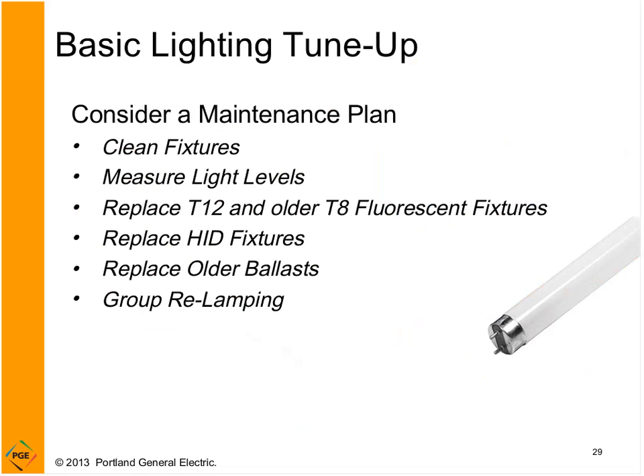Moving on to maintenance of lighting systems. You want to make sure you clean the fixtures. You can measure light levels to make sure that lighting is adequate. Many times, especially if you've got an older facility, maybe the lighting has been retrofitted, but maybe they did a one-for-one replacement. And many times when that is done, you end up with more light than you really need. And so by measuring light levels, you can tune your lighting. Maybe you can delamp some fixtures. Maybe you can completely eliminate some fixtures, which is going to save you not only energy, but maintenance costs as well, right? You don't have to replace those bulbs.